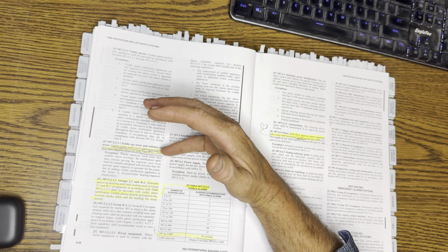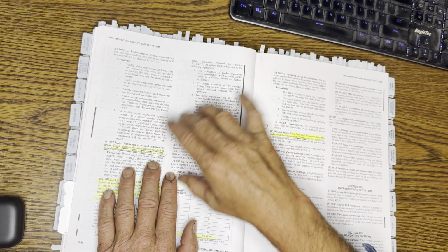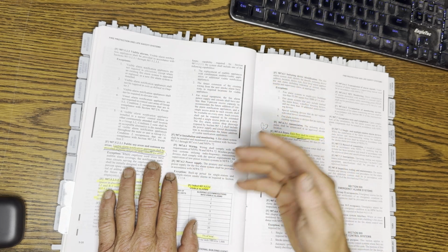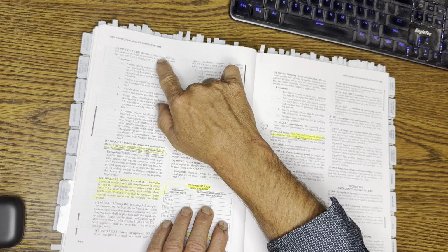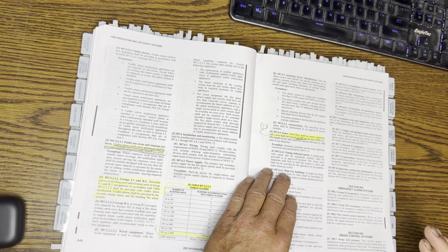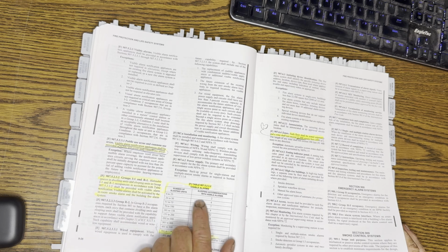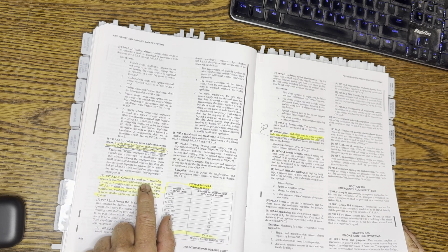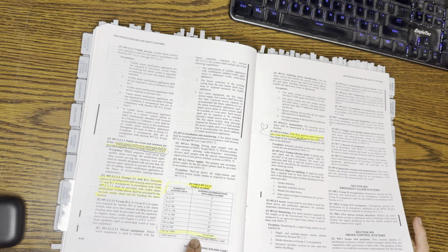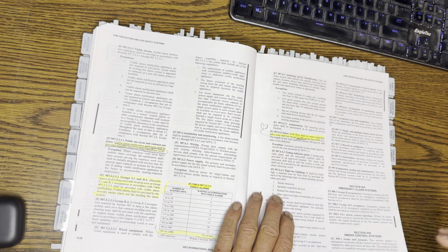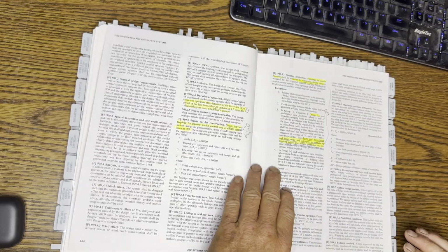Basically, what it means is if you have an office area with more than one person in it, like 2 cubicles or more, you're going to have a visible alarm as well as an audible alarm. Just keep that in mind. And this talks about ADA for our R1, which would be like a hotel. A certain percentage of rooms in hotels have to have visible alarms. It can't be above 22,500 per zone.